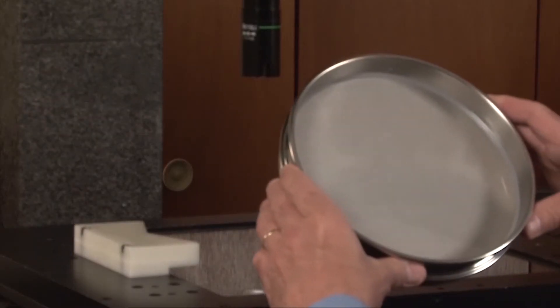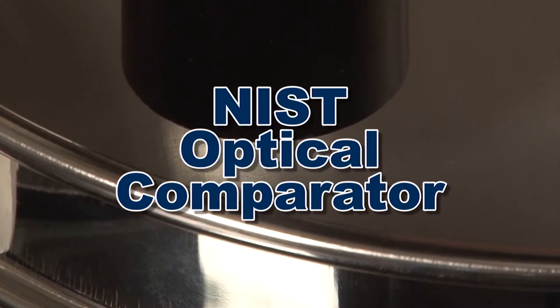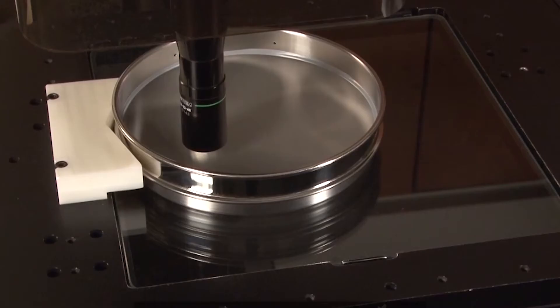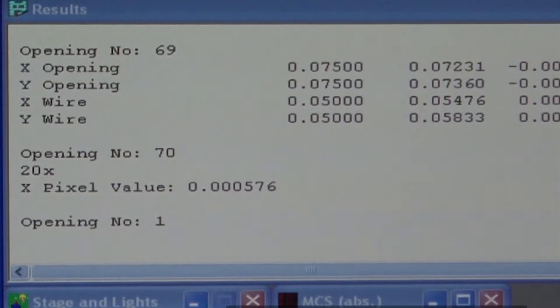Gilson's reverification service individually measures each test sieve or screen tray with an NIST traceable optical comparator.